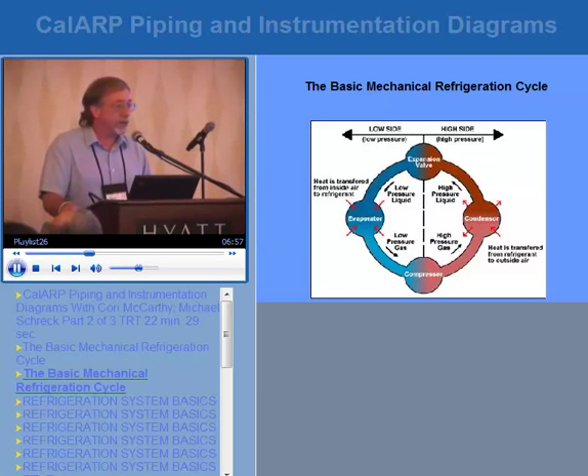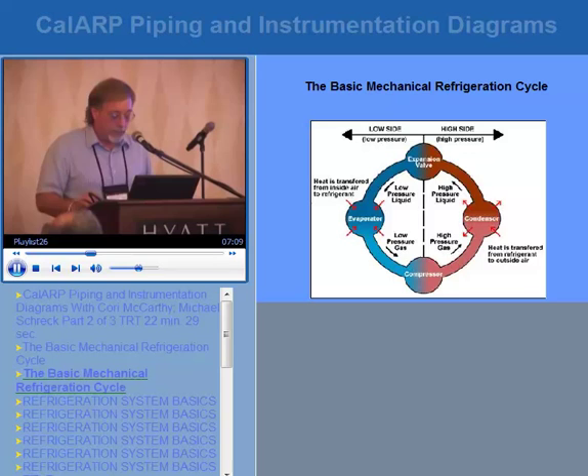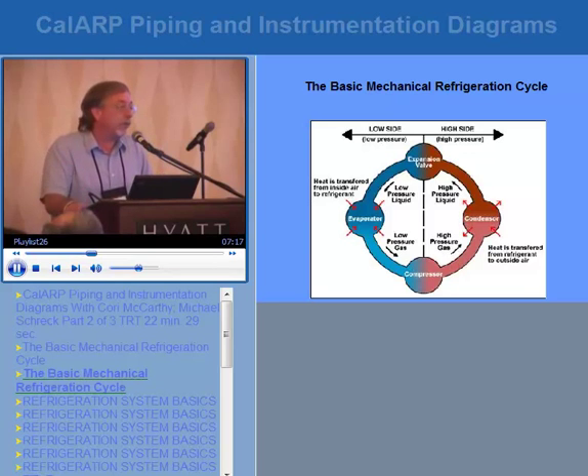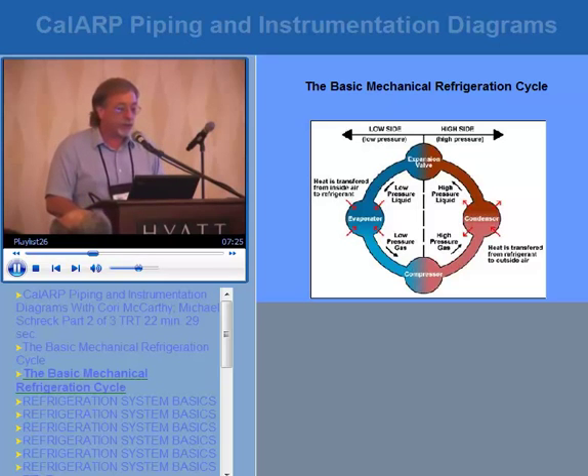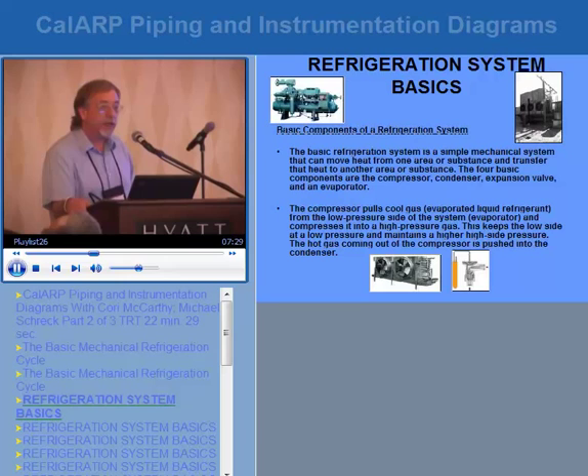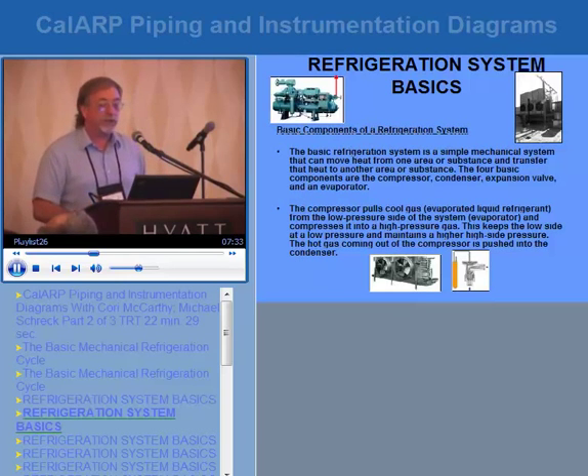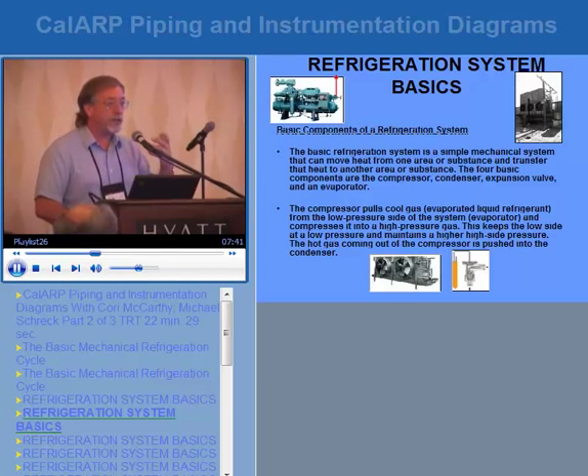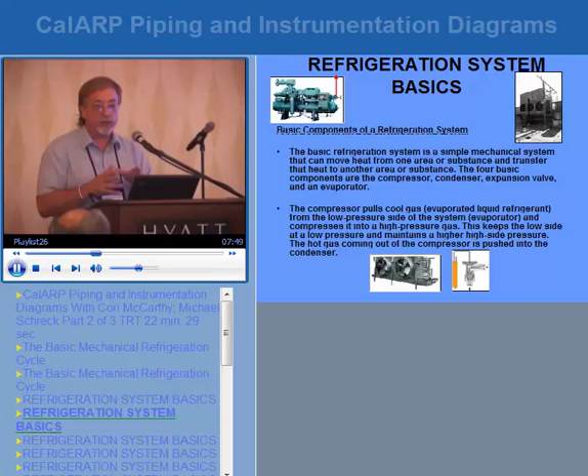P&IDs can be very simple or very detailed depending on the system. Better yet, you can have training documentation where you actually have photos of the equipment along with the P&IDs for training and helping emergency responders. The basic refrigeration system is a simple mechanical system that moves heat from somewhere you don't want it to an area where you can get rid of it or use it for a process. Show the compressor, the high-pressure gas going to the condenser — typically an evaporative condenser — and follow the lines to make an educated assessment of P&ID quality.